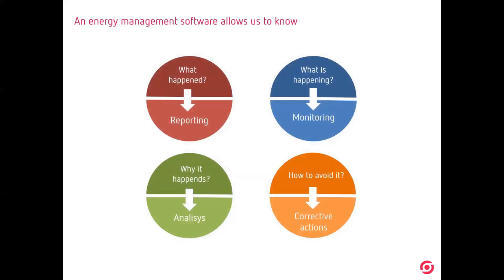We will know what is happening by the real-time monitoring. We will know why it happens by making an analysis of the data that we have in the database. And we will know how to avoid it; we'll know how to make corrective action. If we are paying penalties for reactive, we will know that we have to install a capacitor bank. If we are detecting harmonics that are creating damage on the installation, unexpected trippings, whatever, we will need an active filter. If we are having residual current leakage that is tripping the protection, we will need to change the protection to ultra-immunized or to type B or whatever. So by having all that information, we'll be able to decide. And the idea of the EMS software is to have information to decide and to improve the efficiency and to decrease the bill.